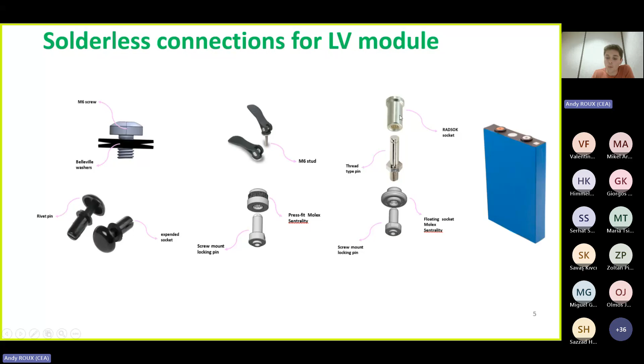So we have 2 kinds of Molex pin and socket. The difference is that on the floating socket we have 1 millimeter adjustment, which permits slight movement of the pin or the bus bar, depending on what moves. The other one is a Radsok solution. It's kind of the same — you have a pin and a socket, but the contact is made differently inside the socket, and this is what we want to compare.